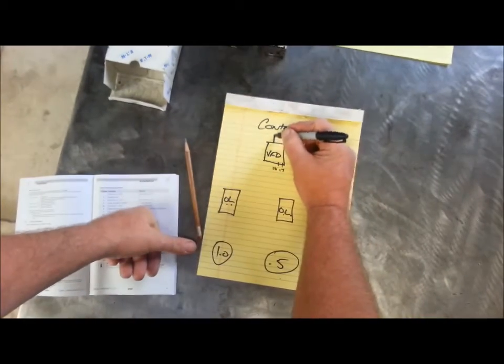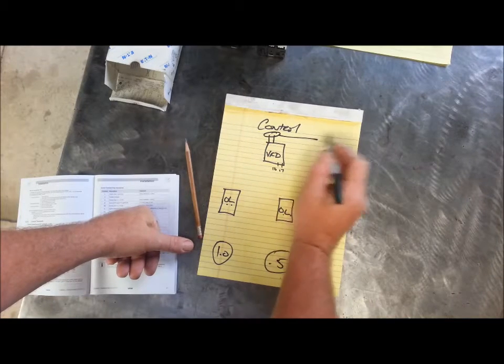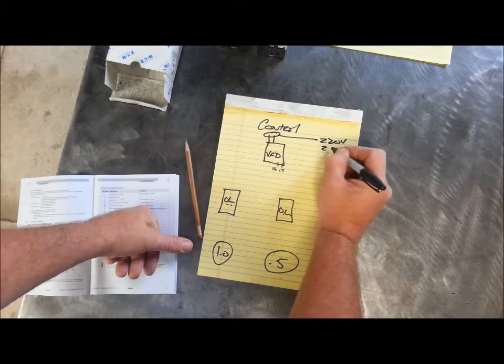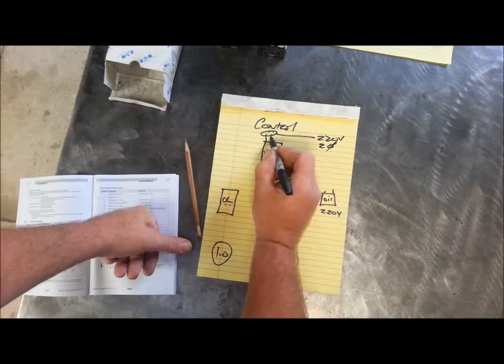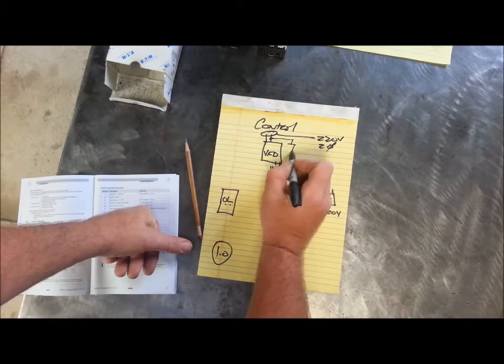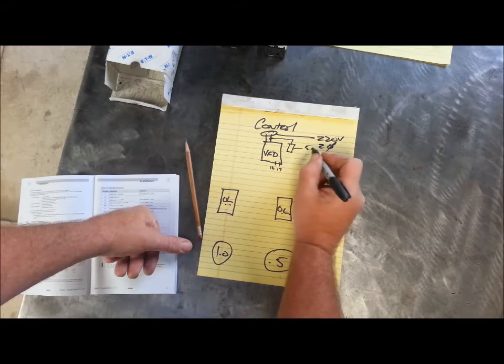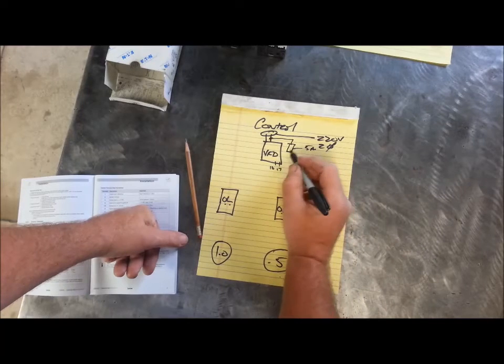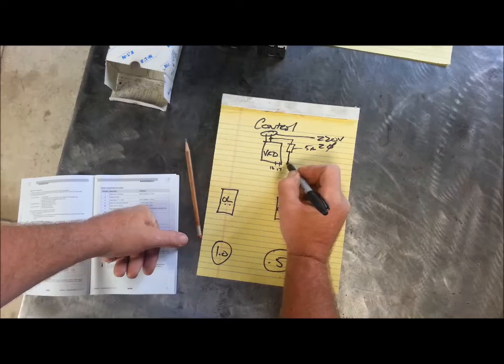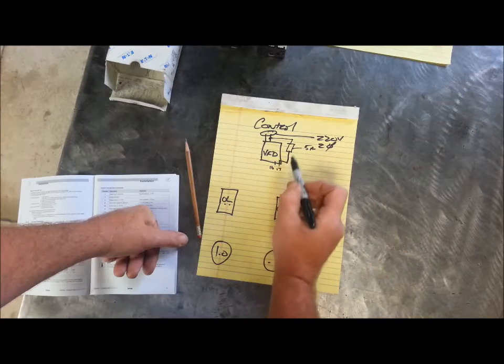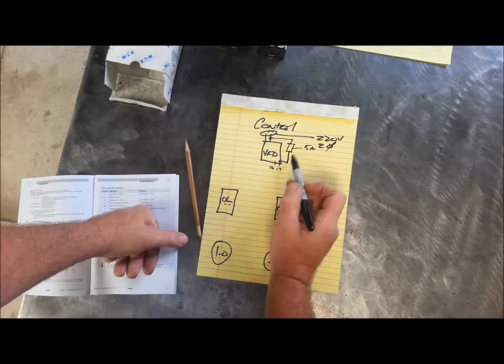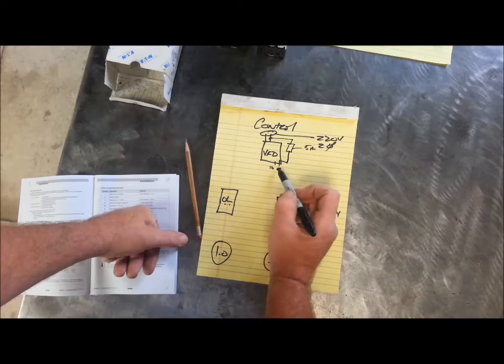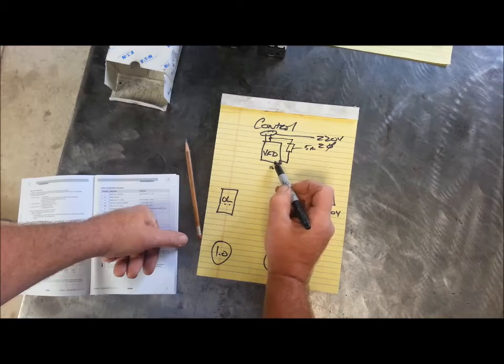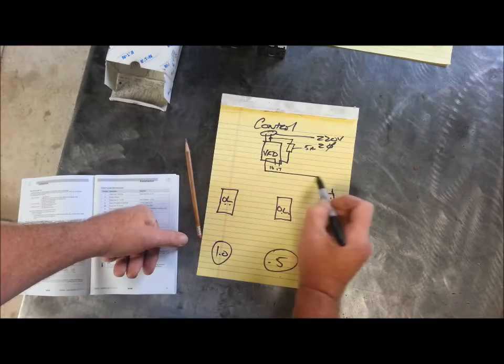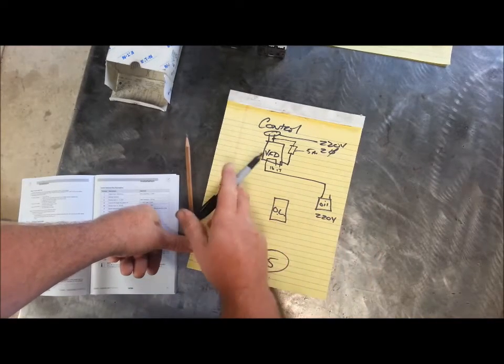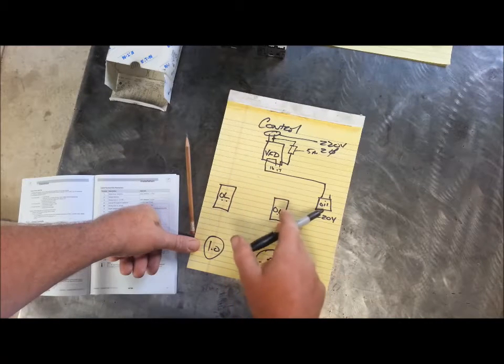So remember we got our 220 volt two phase in here, and we're going to come off of one of these legs and put in a small fuse. This could be maybe a 5 amp fuse. Then we're going to come down to terminal 17, and put one leg of the 220 to this. Off the other one, we're going to come out and go to our oiler. So now when the VFD is given a run command, this switch closes and we power up the oiler.